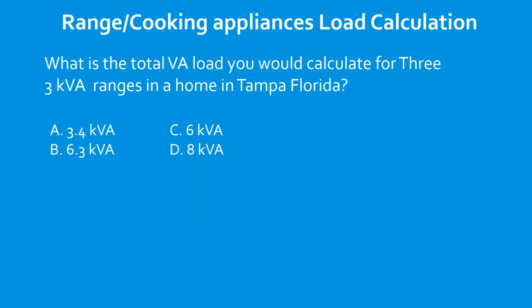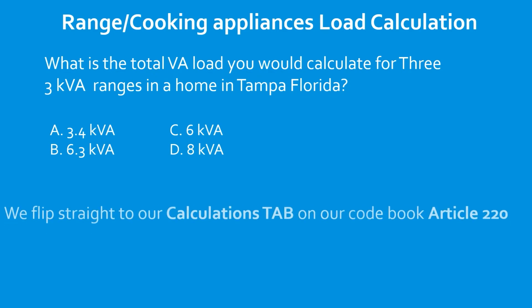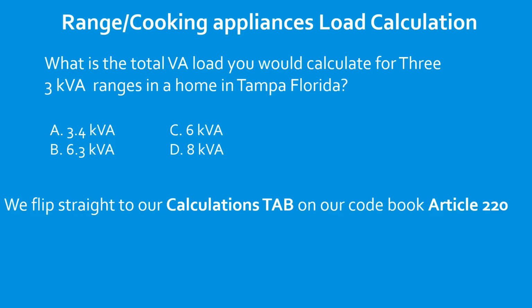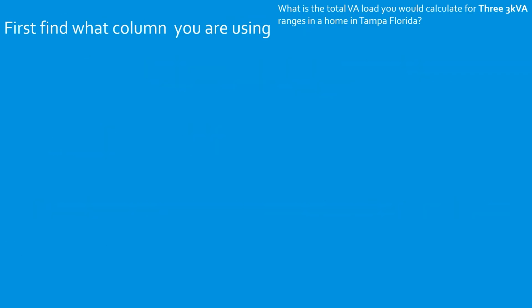What is the total VA load you would calculate for three 3 kVA ranges in a home in Tampa, Florida? So we're going to flip straight to our calculations tab, straight to Article 220. I want us to get in the habit that any time it has to do with the load calculation, we head straight to Article 220, and then we're going to become pros at flipping straight to Table 220.55 when we're dealing with ranges. All right, so the first thing we establish is what column are we using? Always reread your question. What is the total load you would calculate? We have 3 kVA ranges. So what column are we using? We head to Table 220.55, and I think we're going to be using column A because our ranges individually are rated less than 3.5 kW. So we're going to be using column A.